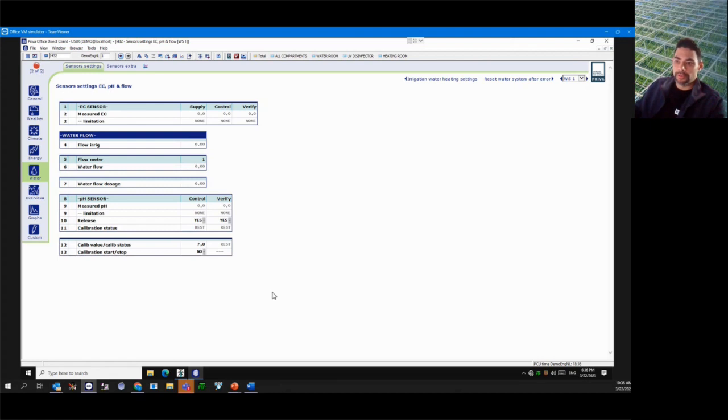When you move it from 7 to 4, you should rinse your sensor. You should just rinse it with distilled water, and then you put it in 4, and you have to wait a couple of minutes. Once you do this, you hit yes. I won't do it just because it's a simulator. When you hit yes, it'll go through its calibration. It'll say good 7 if it worked.